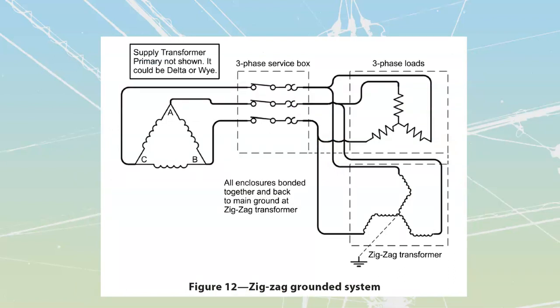What you can do instead is use zigzag grounding to clear on a single fault. A zigzag transformer is a specialized transformer with opposing windings going across each phase. We have B phase going across, with arrowheads going into the center, and C phase arrowheads going into the center as well. Because of the unique way these windings are tied together, we get cancellation of flux.